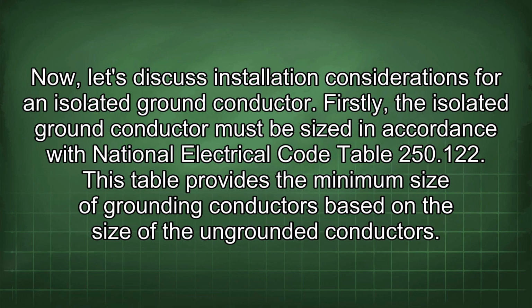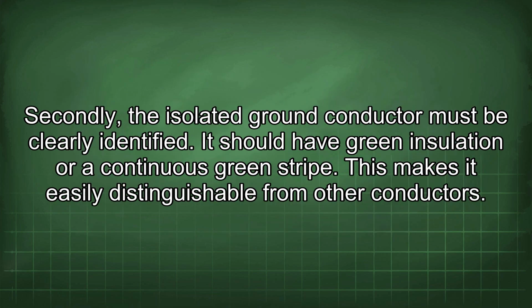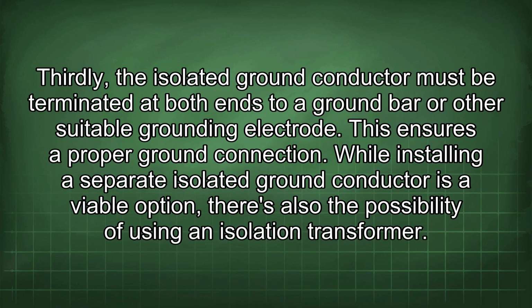Now, let's discuss installation considerations for an isolated ground conductor. Firstly, the isolated ground conductor must be sized in accordance with National Electrical Code Table 250.122. This table provides the minimum size of grounding conductors based on the size of the ungrounded conductors. Secondly, the isolated ground conductor must be clearly identified. It should have green insulation or a continuous green stripe. This makes it easily distinguishable from other conductors. Thirdly, the isolated ground conductor must be terminated at both ends to a ground bar or other suitable grounding electrode. This ensures a proper ground connection.